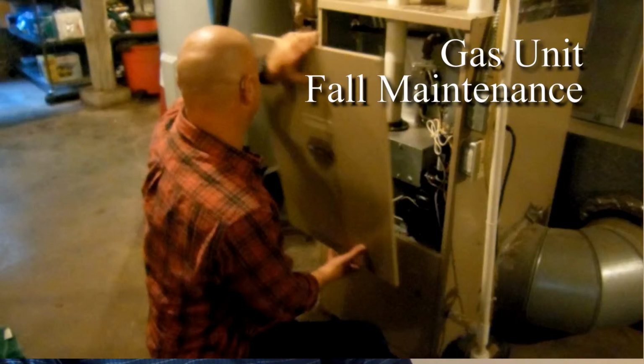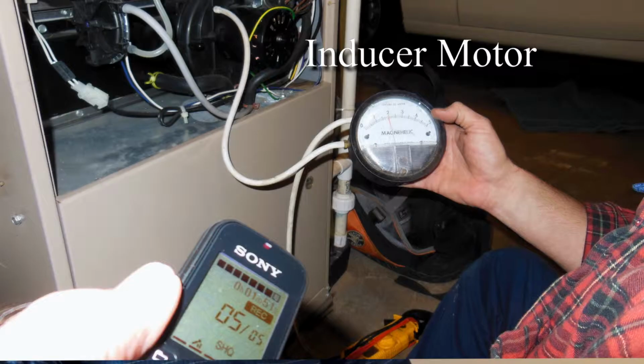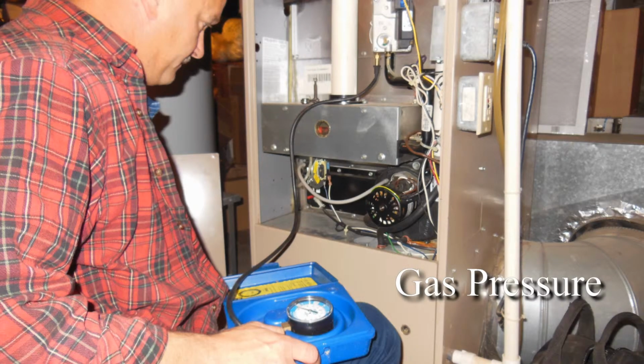On a gas unit, we check the inducer motor to make sure that it's drawing the proper amount of air through the heat exchanger so the gas will burn properly. We check the gas pressure coming out of the gas valve to make sure that the gas pressure is at the proper pressure. We check the heat exchanger to make sure that there are no holes or cracks in the heat exchanger so that we keep carbon monoxide out of the house.